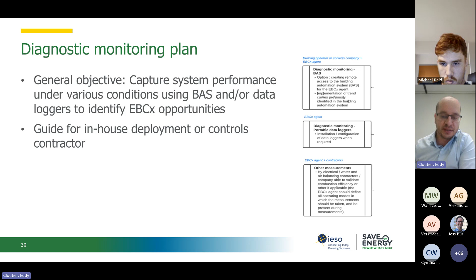Typically, diagnostic monitoring will generally aim to collect precise and detailed data on the following elements. So first of all, of course, energy consumption. When you already have existing energy meters and sub-meters, often the building manager already has monthly data for these meters, but what often interests us in existing building commissioning is to have more granular data, for example, every hour or every 15 minutes, which makes it possible to detect anomalies impossible to see with monthly data, or very difficult to detect.